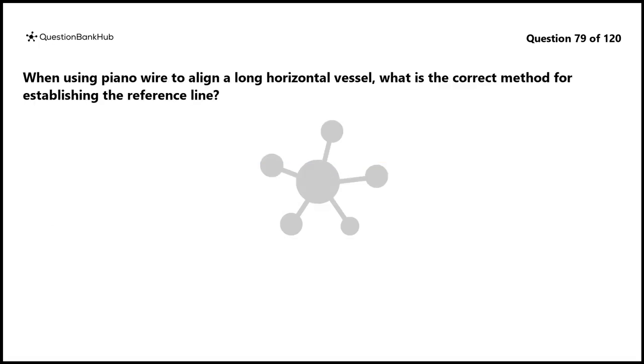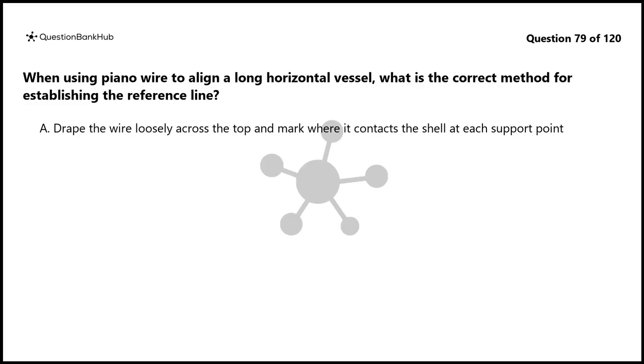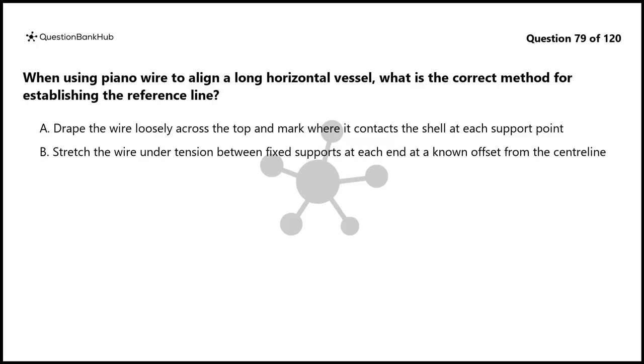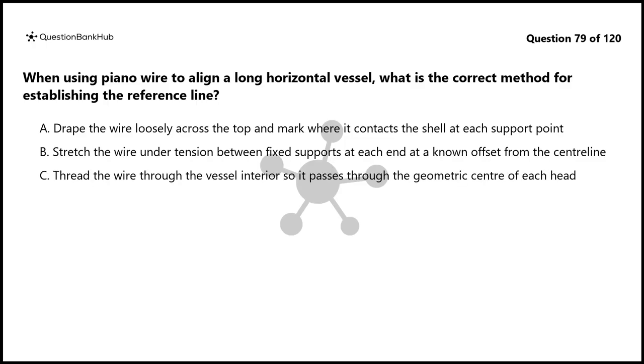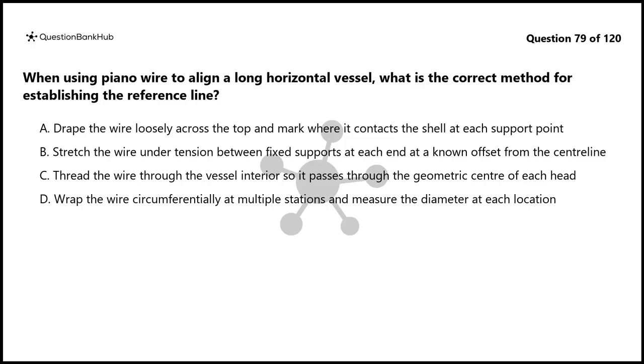Question 79. When using piano wire to align a long horizontal vessel, what is the correct method for establishing the reference line? A. Drape the wire loosely across the top and mark where it contacts the shell at each support point. B. Stretch the wire under tension between fixed supports at each end at a known offset from the center line. C. Thread the wire through the vessel interior so it passes through the geometric center of each head. D. Wrap the wire circumferentially at multiple stations and measure the diameter at each location.